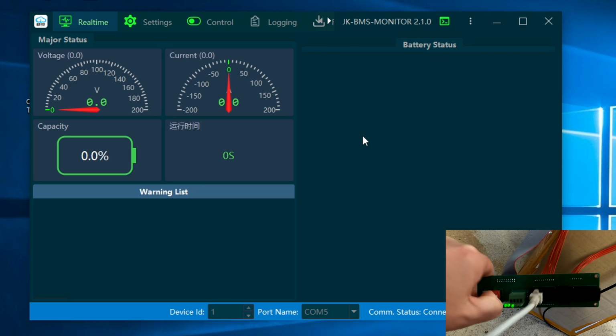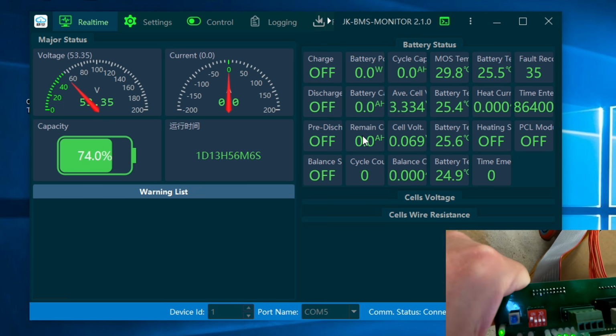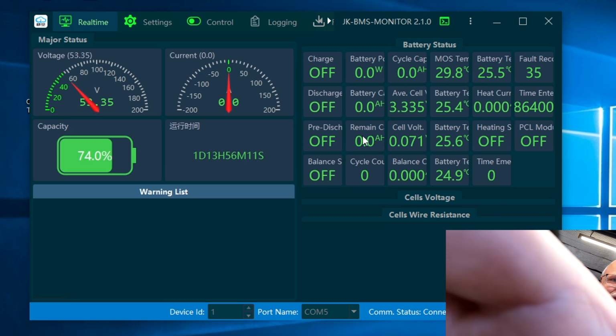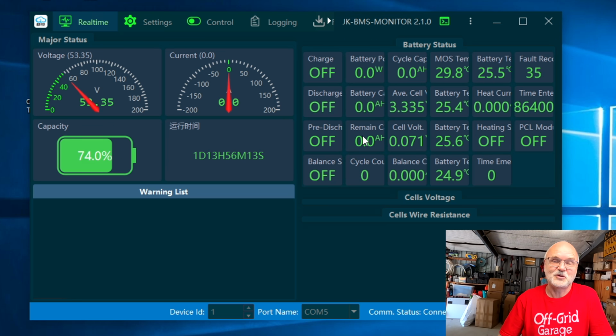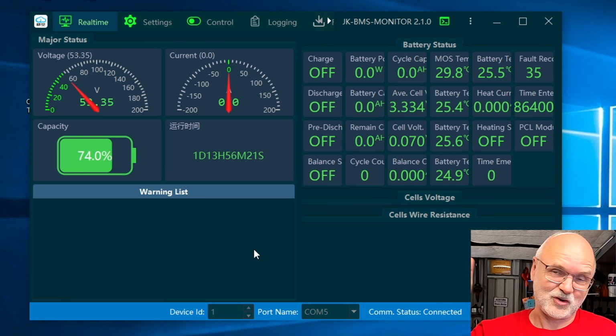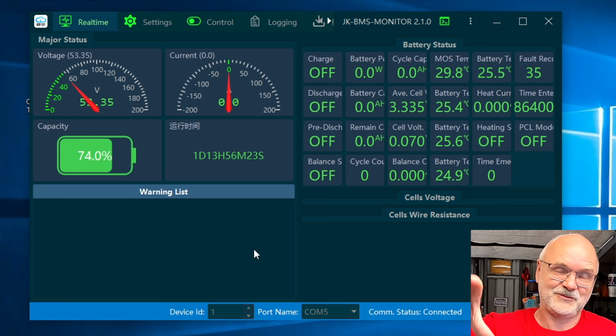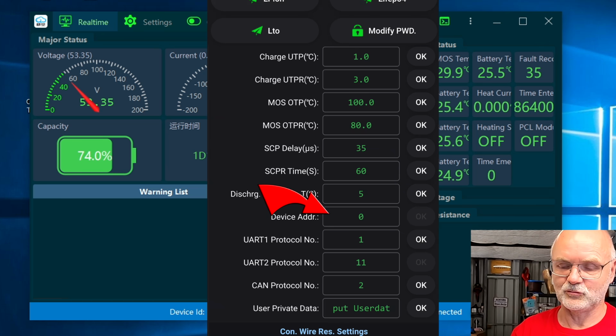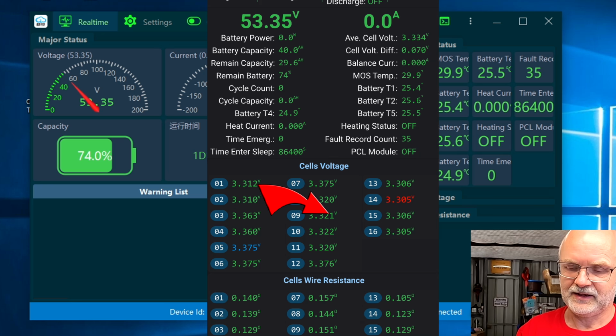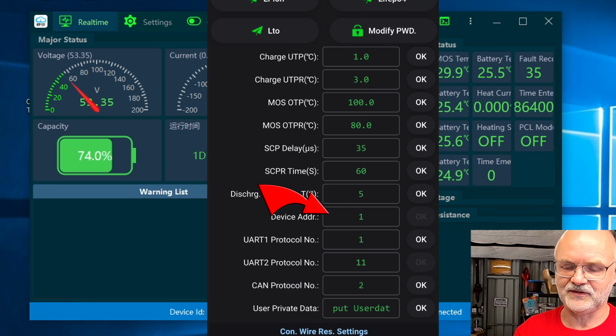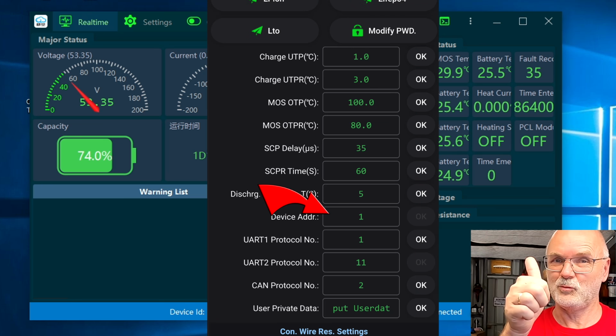I turned on dip switch number 1, like this, and as soon as I did, the communication established. Now the communication is running between the BMS and the computer software. If we do a refresh on the app, left and right, we can see the device address has now changed to number 1.